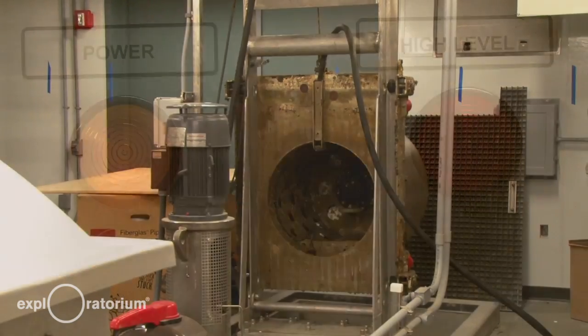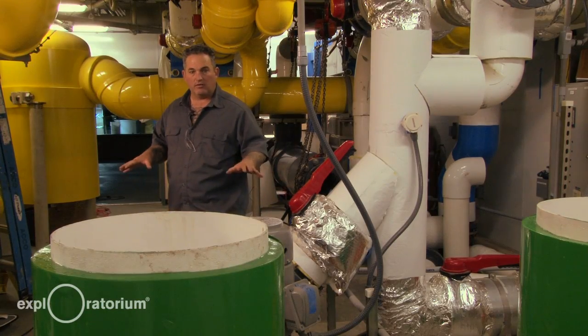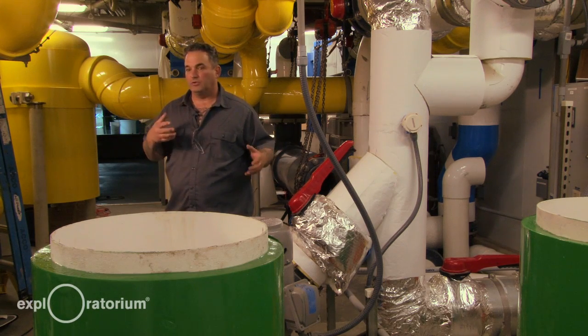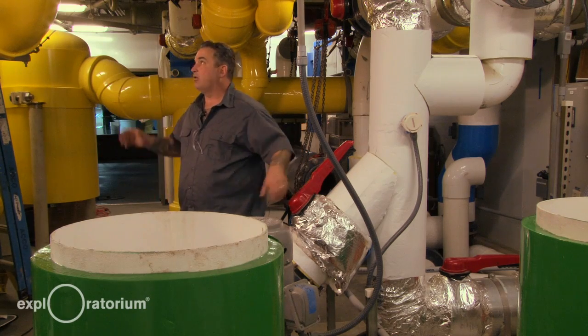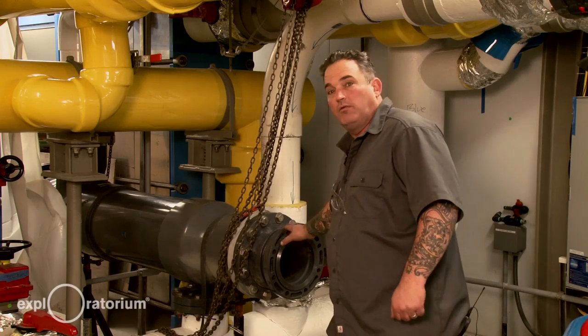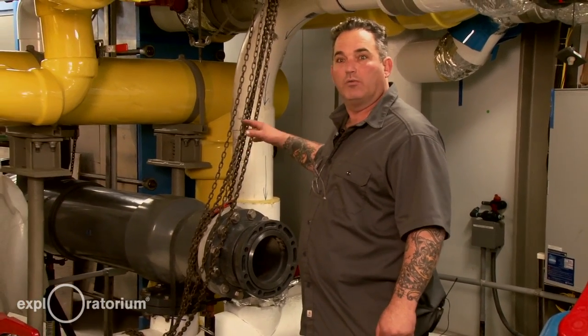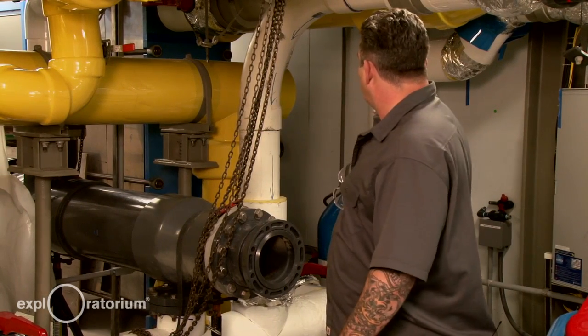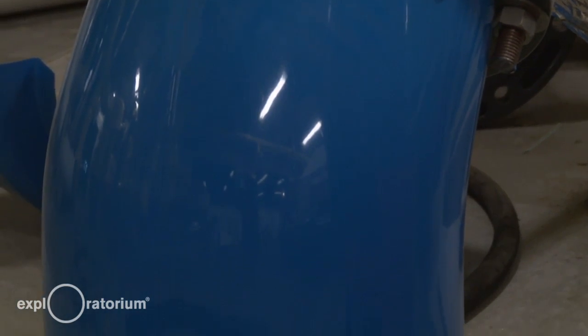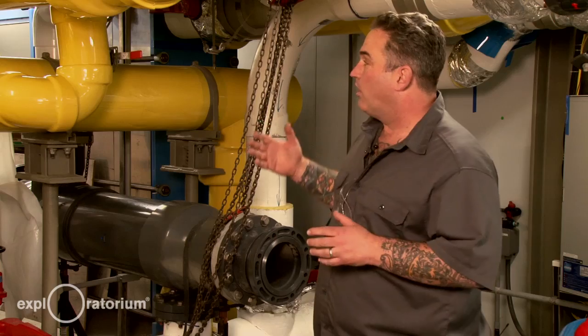From there, that 55-degree seawater has now been filtered down to about 30 microns, and it ends up in a holding tank below — hundreds and hundreds of gallons — holding that 55-degree water. When the building is calling for it and drawing that seawater up, it comes up through the large pipes below me. This is the very last filter: it uses ultraviolet light to get the last bit of biological life out of the seawater. All the green piping coming in here is seawater, and it's all plastic pipe going into those two giant blue heat exchangers back there.